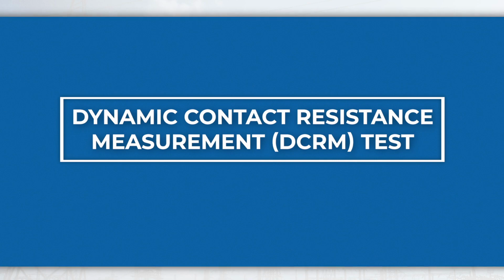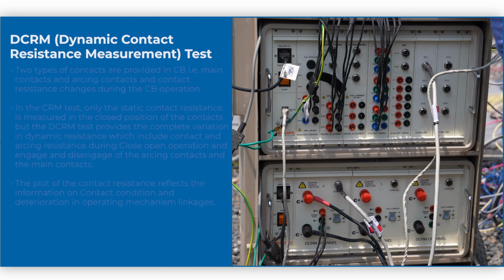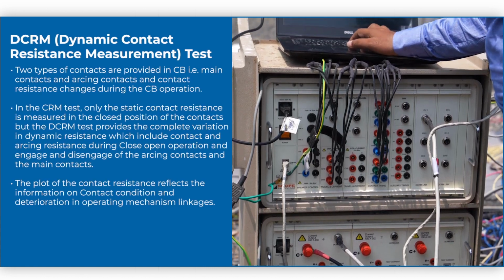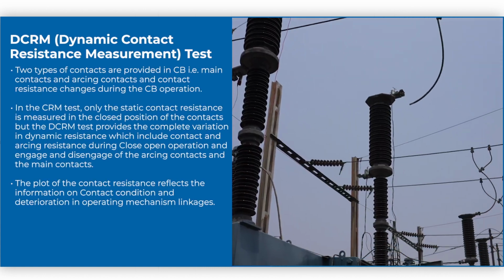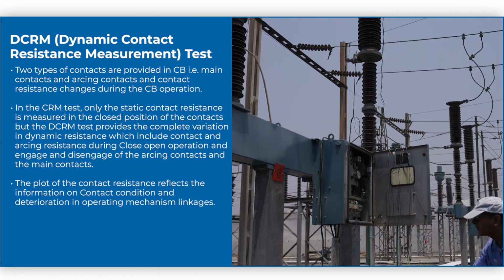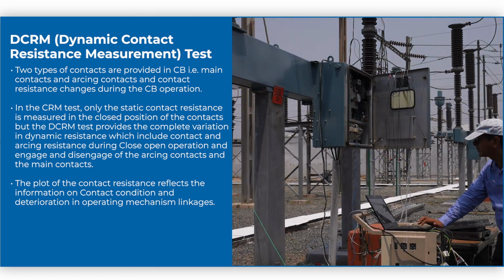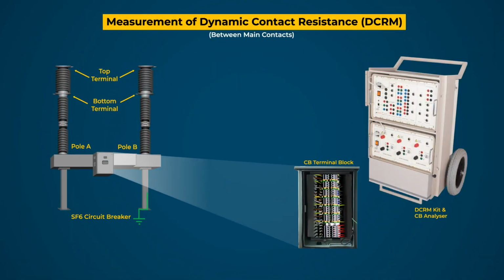Dynamic Contact Resistance Measurement (DCRM) test. The DCRM test provides the complete variation in dynamic resistance, which includes contact and arcing resistance during close-open operation. Steps for testing. First, open the connections of both end terminal connectors.